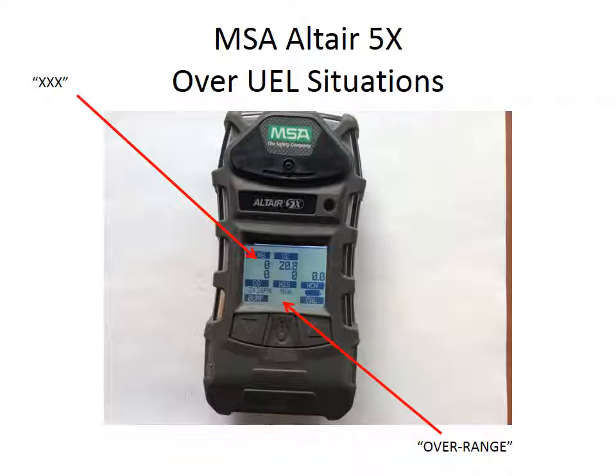Okay, next question comes about how this meter functions if I'm in a situation where it's over the UEL. Like I mentioned before, that's still a dangerous situation because we can go back down into that flammable range. So what's going to happen if I'm over UEL? Is the meter going to tell me that? Well, it is going to do that. You're going to go into alarm, and at the combustible gas reading, you're going to see the XXX. But at the bottom, between the bump and cal, with those indicators at the bottom of the screen, you're going to see a flag come up: over range. Okay, and that over range is telling you you're over the UEL.